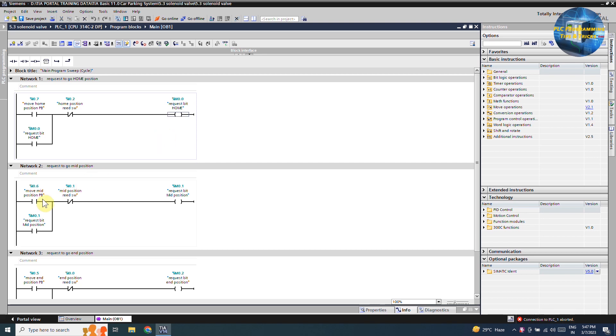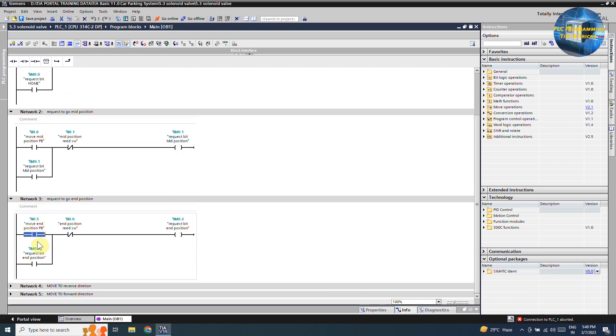In network 2, if we press the mid position push button i0.6 and the cylinder position is not at the mid position reed switch i0.1, it will latch on the request bit mid position m0.1. In network 3, if we press the end position button i0.5 and the cylinder piston is not at the end position reed switch i0.0, it will latch on the request bit end position m0.2.